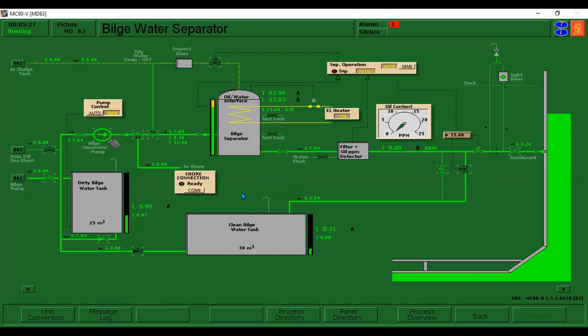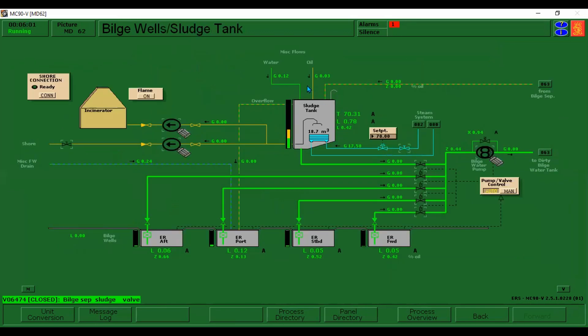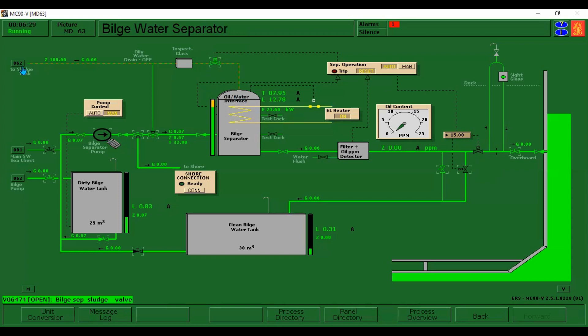If you switch off the bilge pump, the thermostatic valve will be automatically closed and deactivated. When placed in automatic mode, the thermostatic valve will also open because the upper part of the bilge oil separator contains oil, so that oil returns to the sludge tank. The water will then be reintroduced going into the bilge oil separator. When the pump is stopped, the thermostatic valve closes, and the oil part goes to the sludge tank. When the pump starts again, the valve activates and water flow resumes.